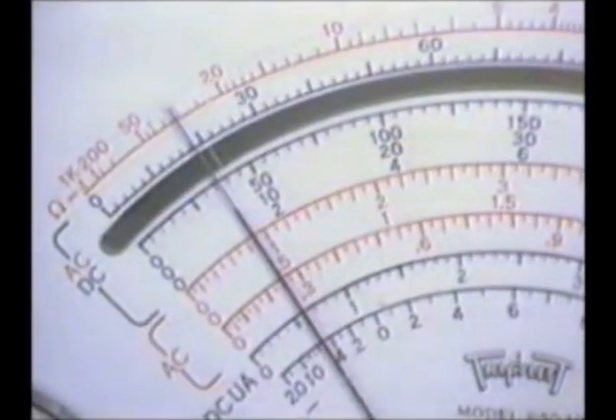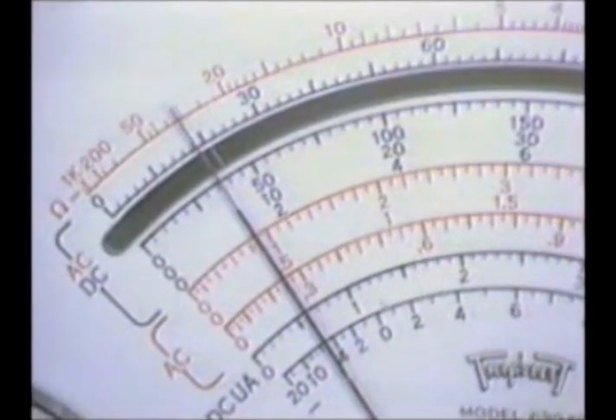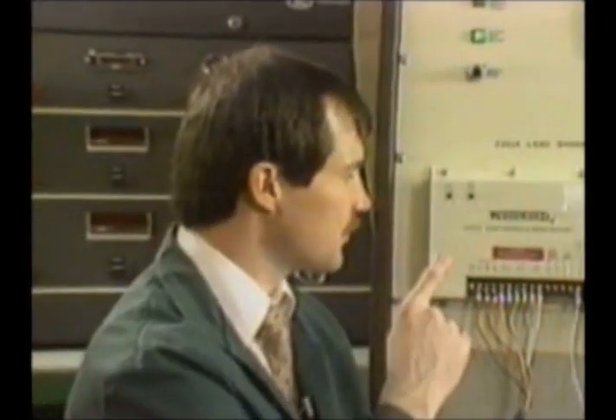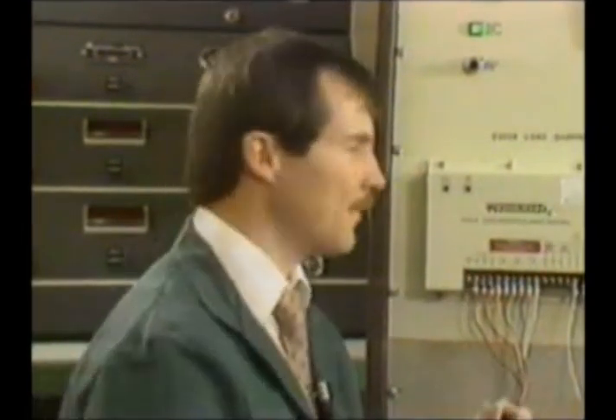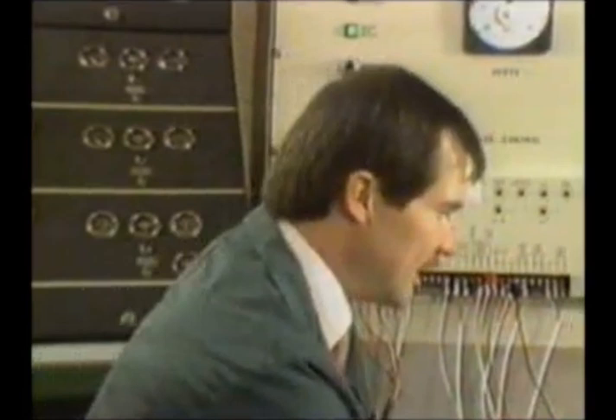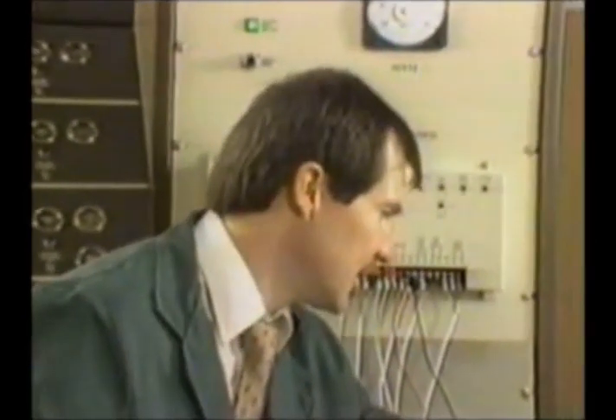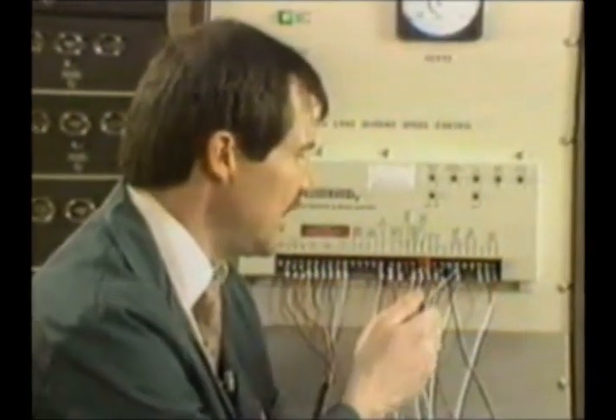And the engine came up stable, so my analog meter just shows what the no load voltage is on the actuator. We're reading just under 2 volts on the analog meter. So now I'm going to want to adjust my gain and reset. Since we're stable already, I still want to show you how to adjust your gain and reset potentiometers for your prime mover. Now I'm going to turn the gain pot clockwise until I get an instability. Let me turn my analog meter down to the next scale so it comes up more in the middle. So now I'm going to turn my gain pot till I get my analog meter to go unstable.